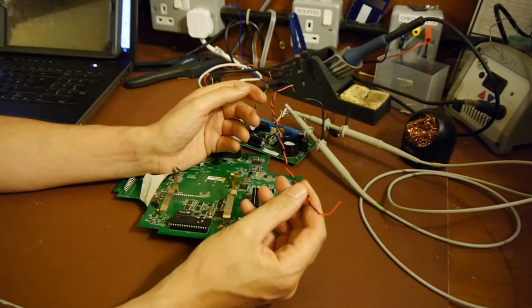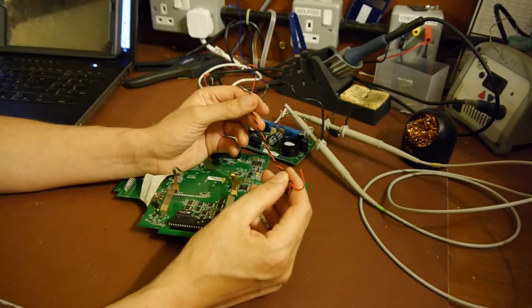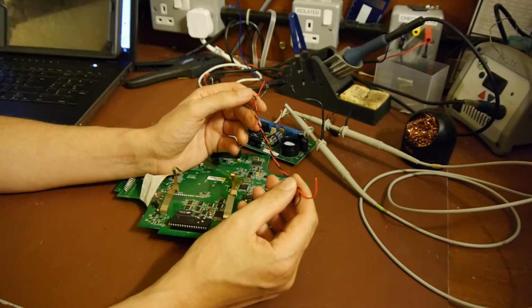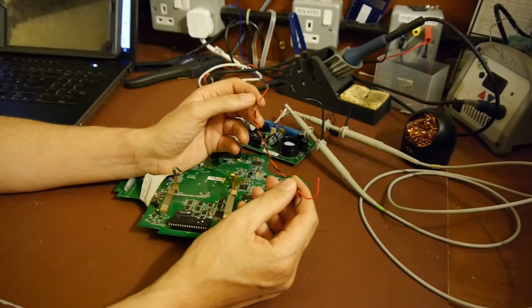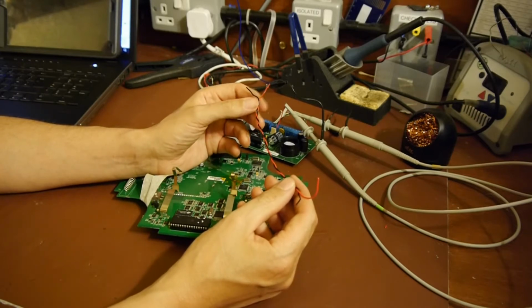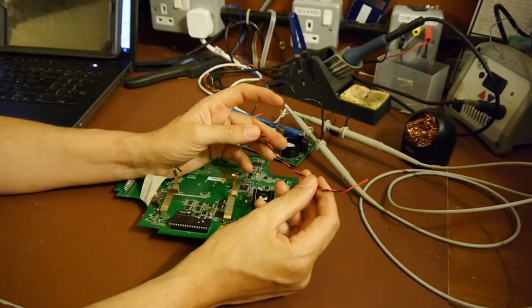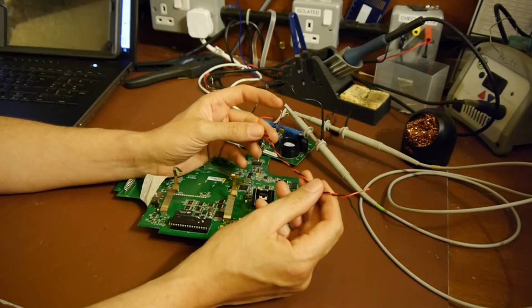You only need one twisted pair. But if you want to do what they call full duplex, which some systems do use, you actually need two twisted pairs. You need a dedicated twisted pair for transmitting and a dedicated twisted pair for receiving. And the advantage for that is that you can transmit and receive at the same time, which can be faster. And some applications you need to do that. But again, twisted pairs go up to 4,000 feet, multi-drop, quite good.